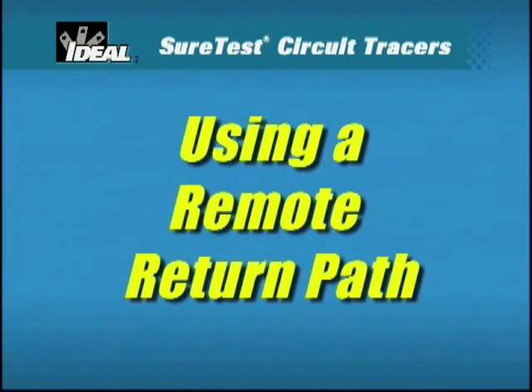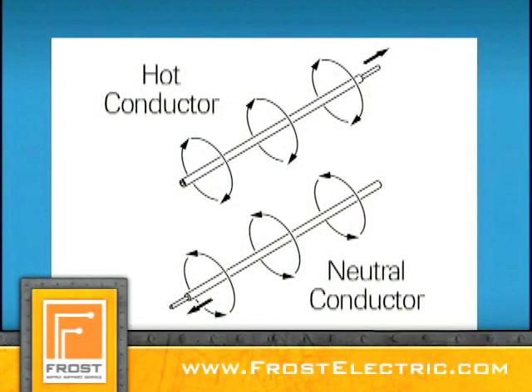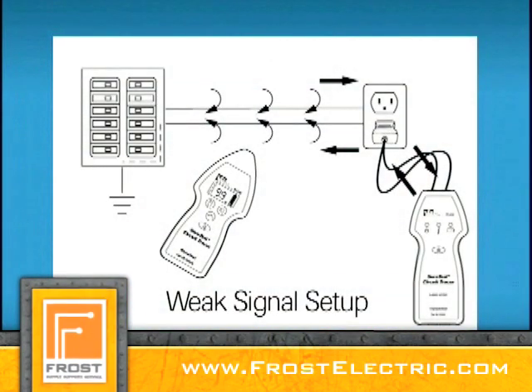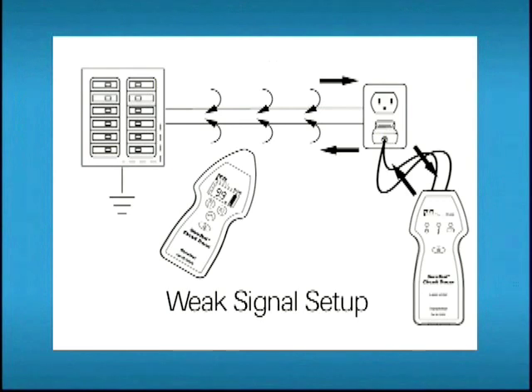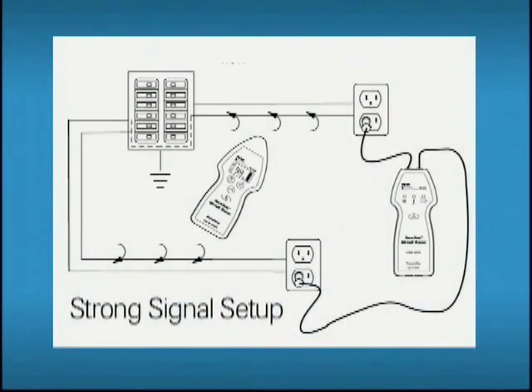The second concept is utilizing a remote return path. When current flows, it creates an electromagnetic field counterclockwise to the direction of current flow. As current flows out on a hot conductor and returns in the opposite direction on a neutral conductor, it creates opposing magnetic fields. If these two wires are close together, the magnetic fields tend to cancel each other out, which diminishes the receiver's ability to detect the signal.